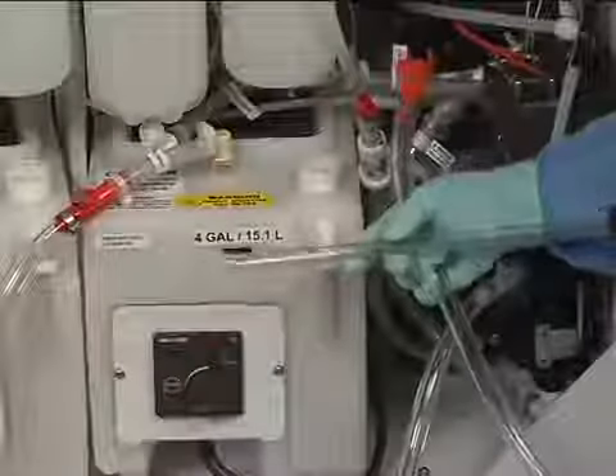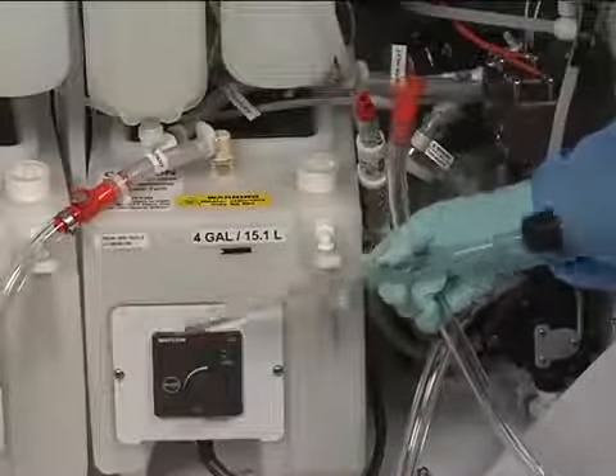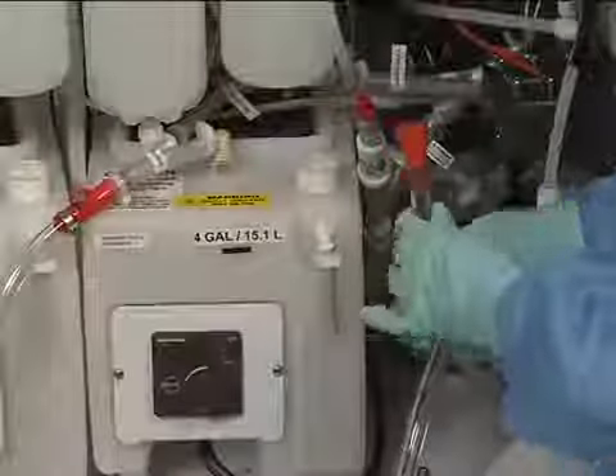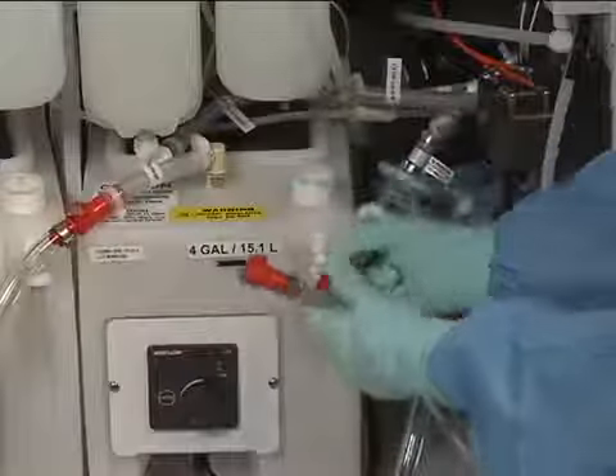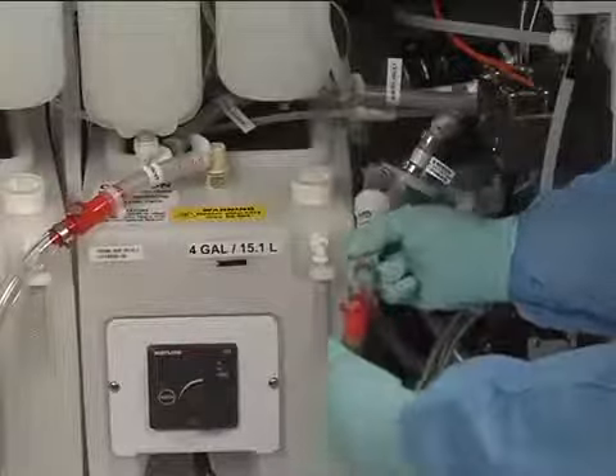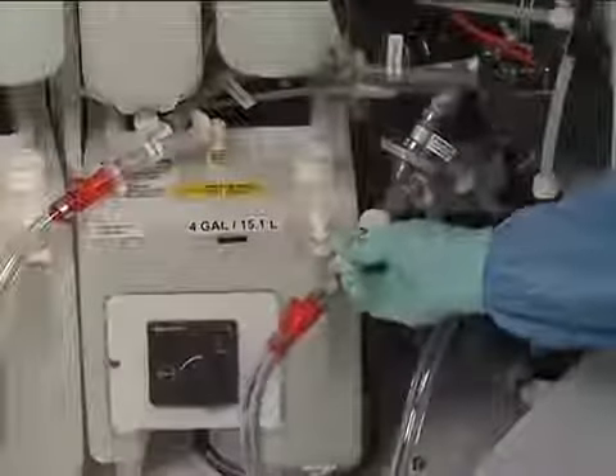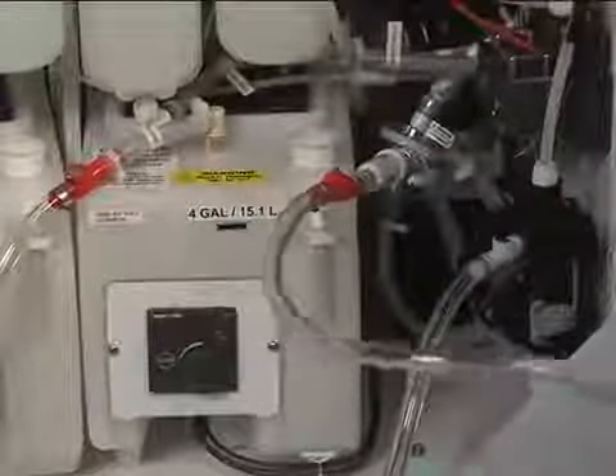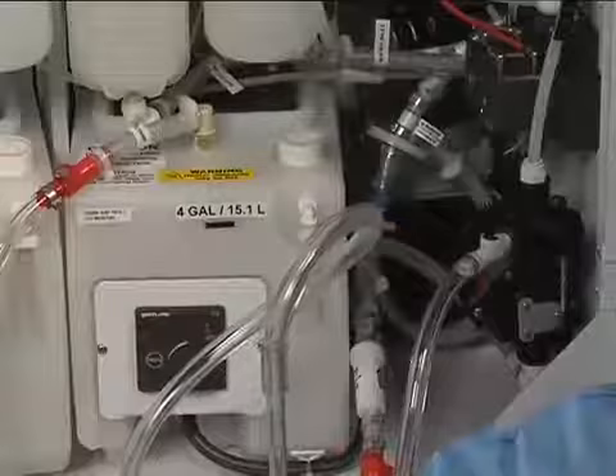Locate the transfer pump tubing segment with the red female end and the long rigid end with rubber seal. Connect the red female end to the male red-colored end of the disinfectant filter. Note, on earlier models, the male end of the disinfectant filter may be cream-colored. Place the rigid end with rubber seal of the transfer pump tubing into a full disinfectant container.